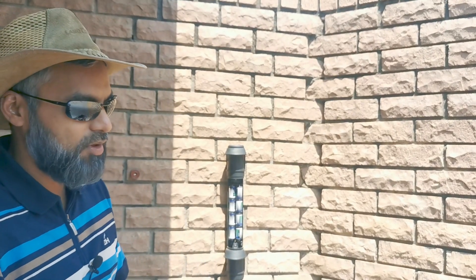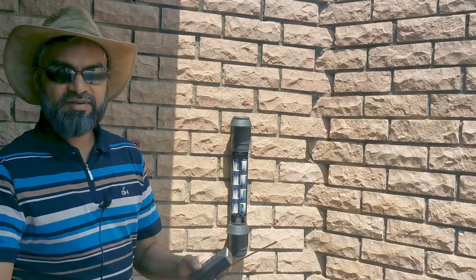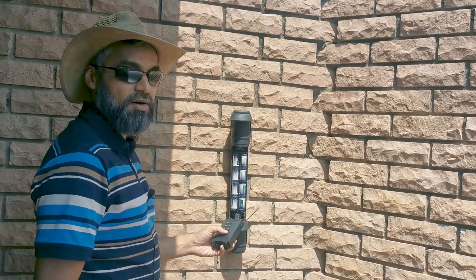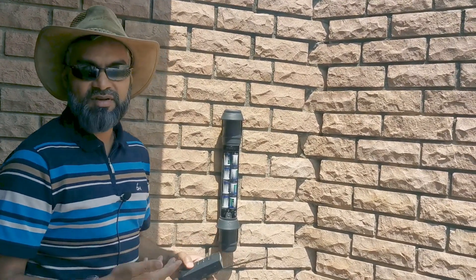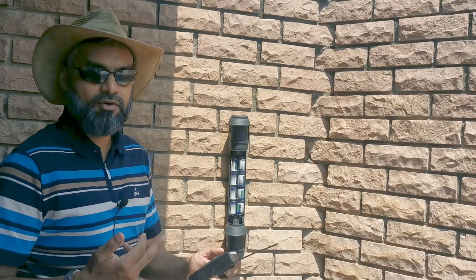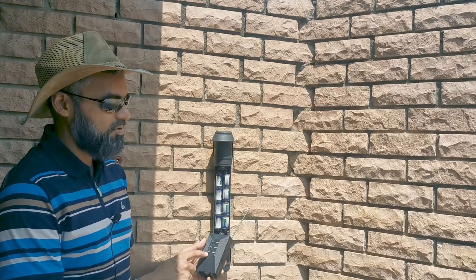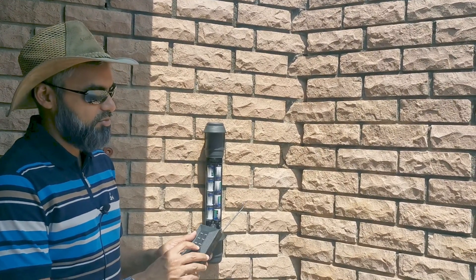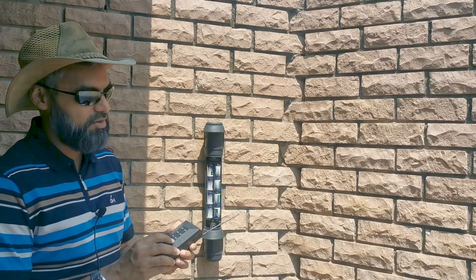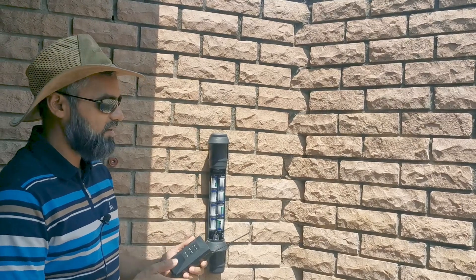Now I just want to show you how to program it back into the HQ in case somebody deleted it — these buttons are quite easy to press unknowingly. If you want to program zone A, tamper is zone A. Status on your HQ — mine says trouble — that's zone B.